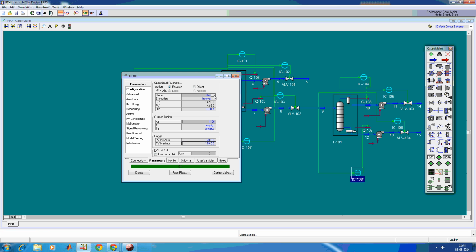If the temperature is increasing, reduce the steam, so that's reverse action. Make it automatic, and we'll just say gain is 2, and this is about 10 minutes. And go to manual, set it to 50% first, and then you convert to automatic. Okay, this is what we have.